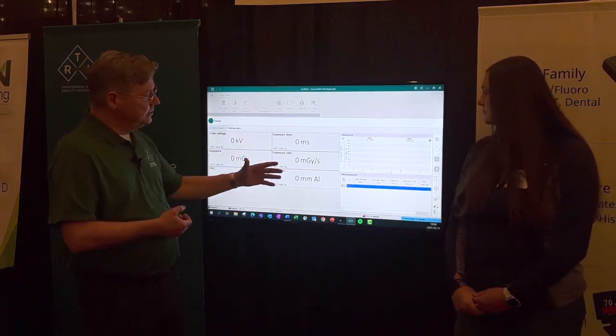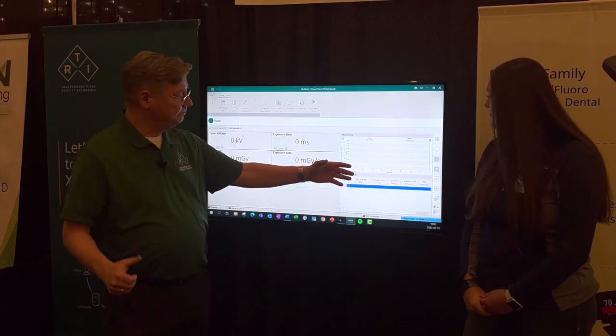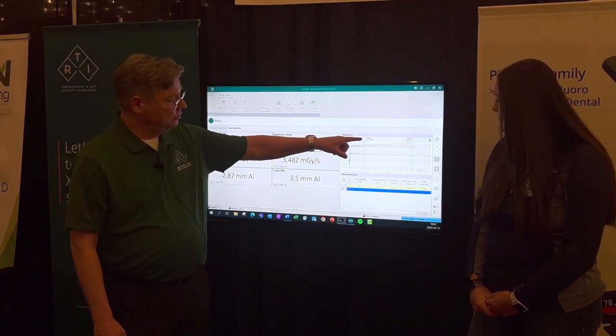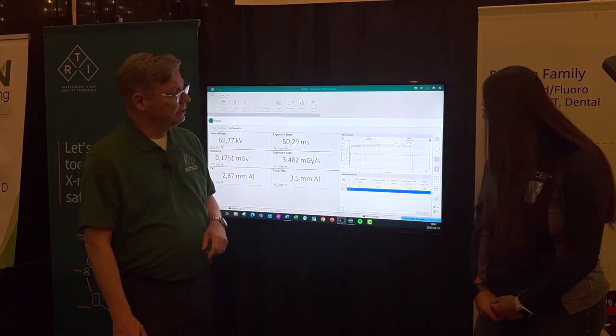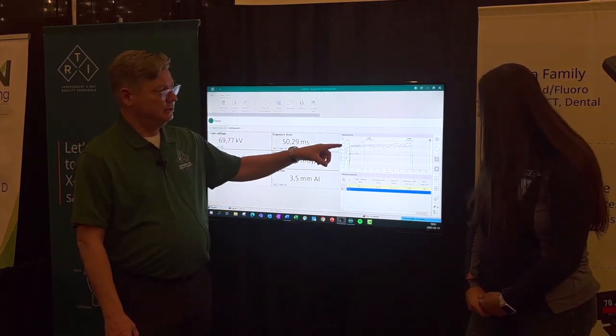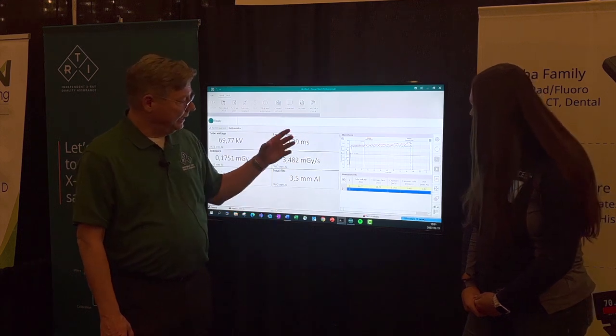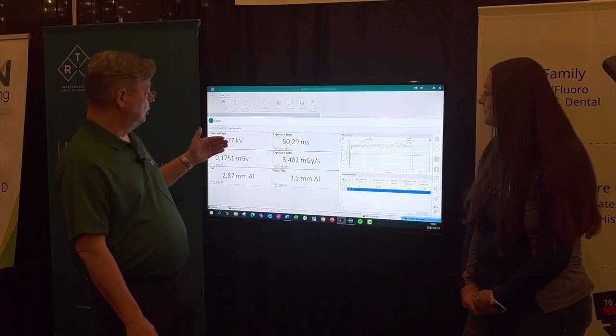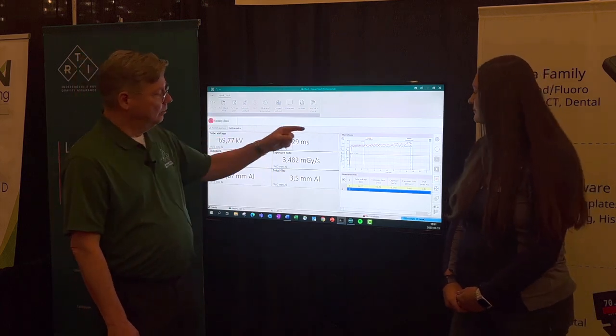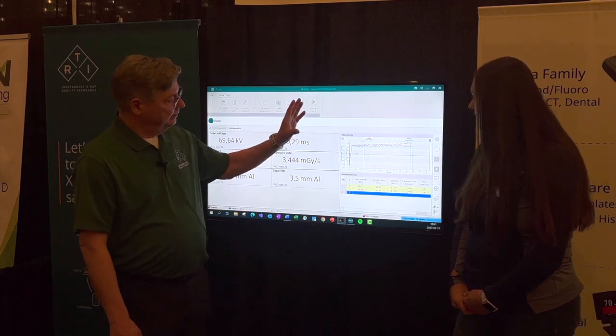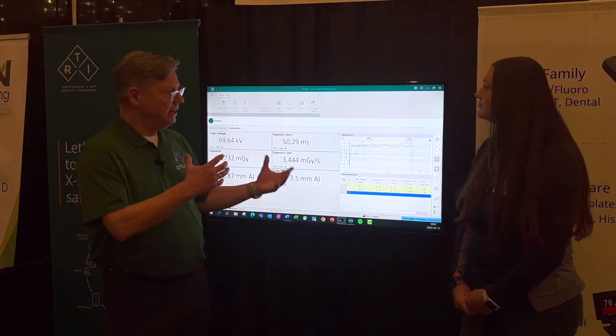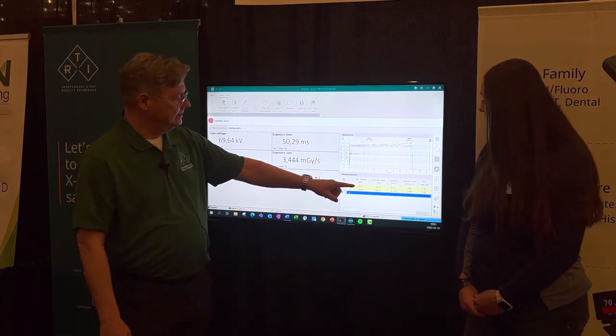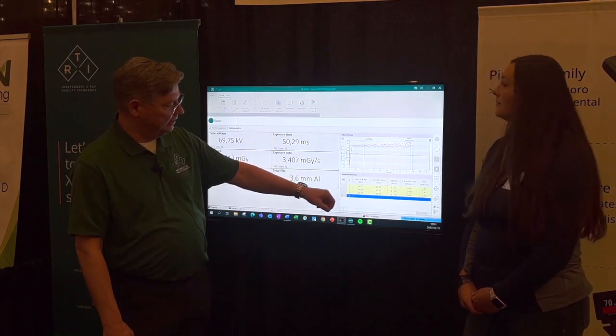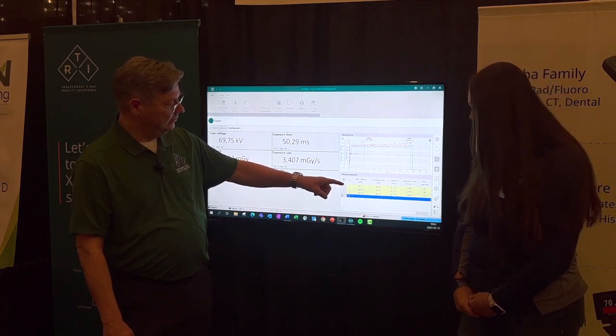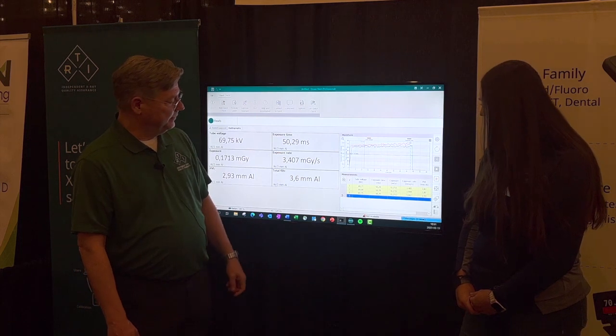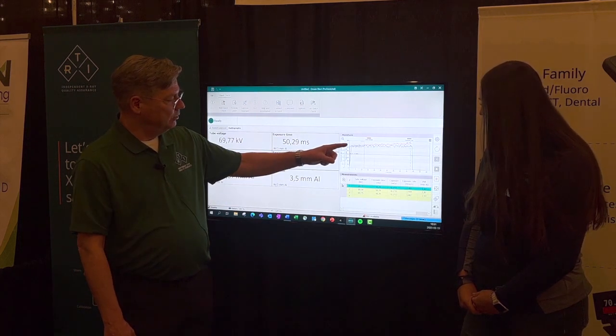And these values can then also be presented in a waveform. So we have it over here, where we can see the tube voltage waveform as well as the exposure rate, the dose rate waveform. So that is actually the output from the tube that we're seeing, and it gives us a very good picture, not only the numbers, but how we arrive at that number. That's incredible. Yeah, and it's good because we can then go back and see how we arrived at 69.77. So we can move back and highlight on that one so we can see that waveform again when we're looking at it. So that's the waveform that we can see.